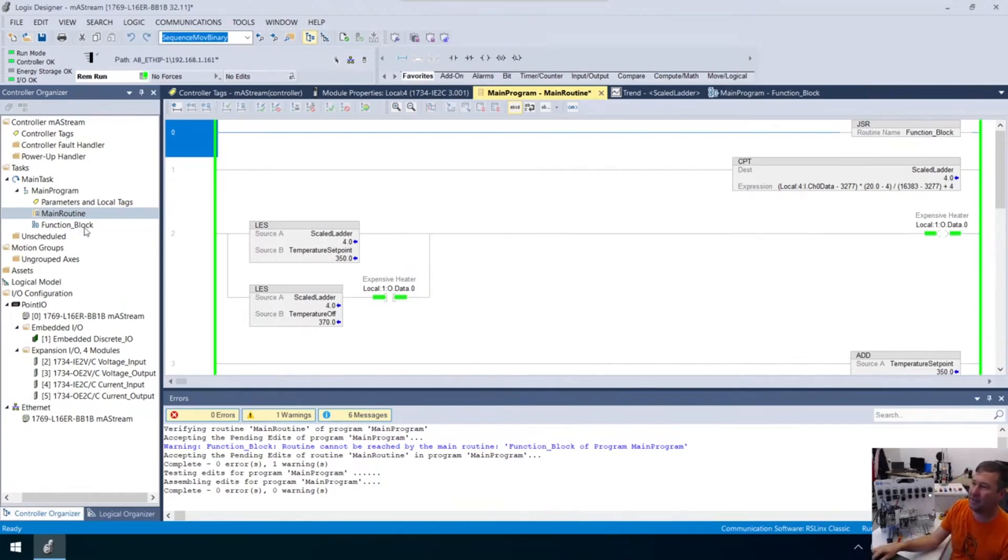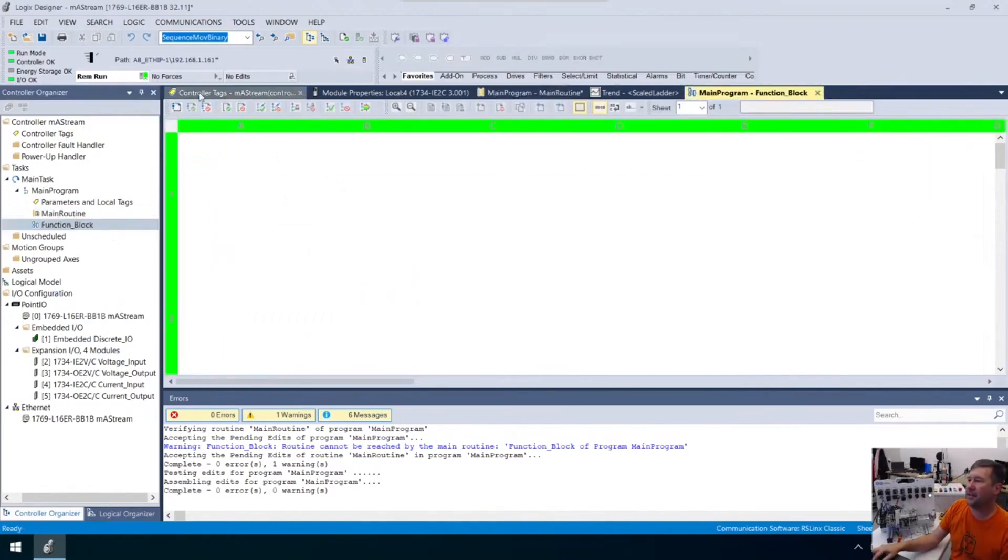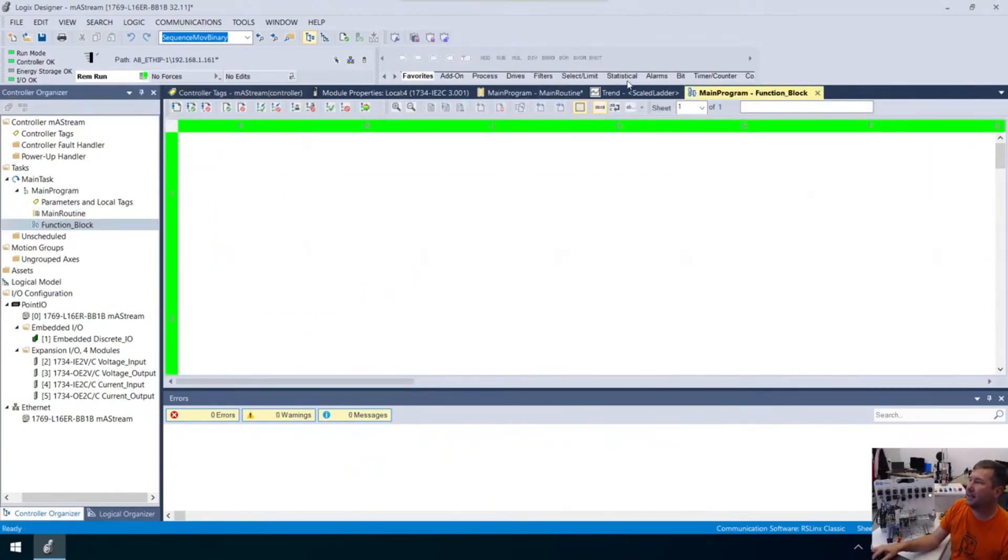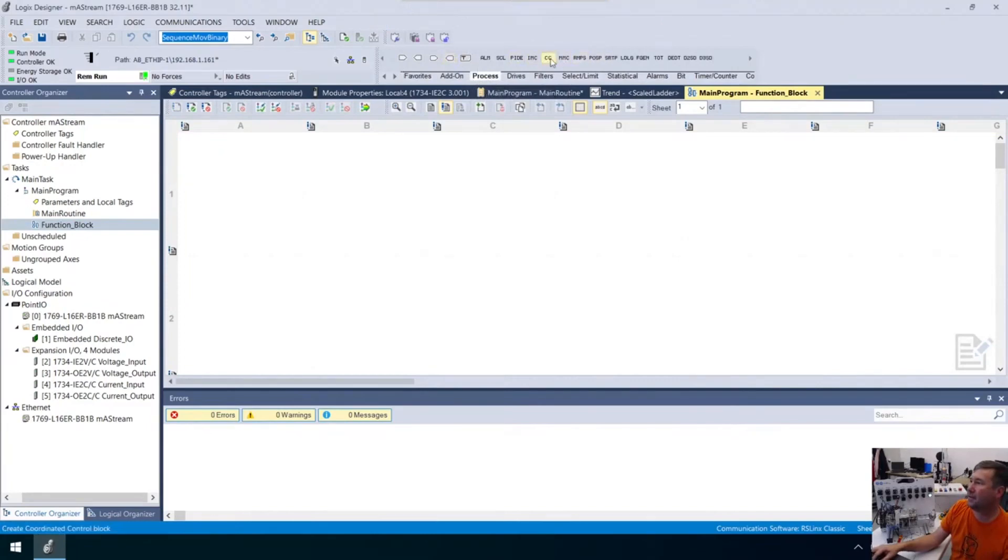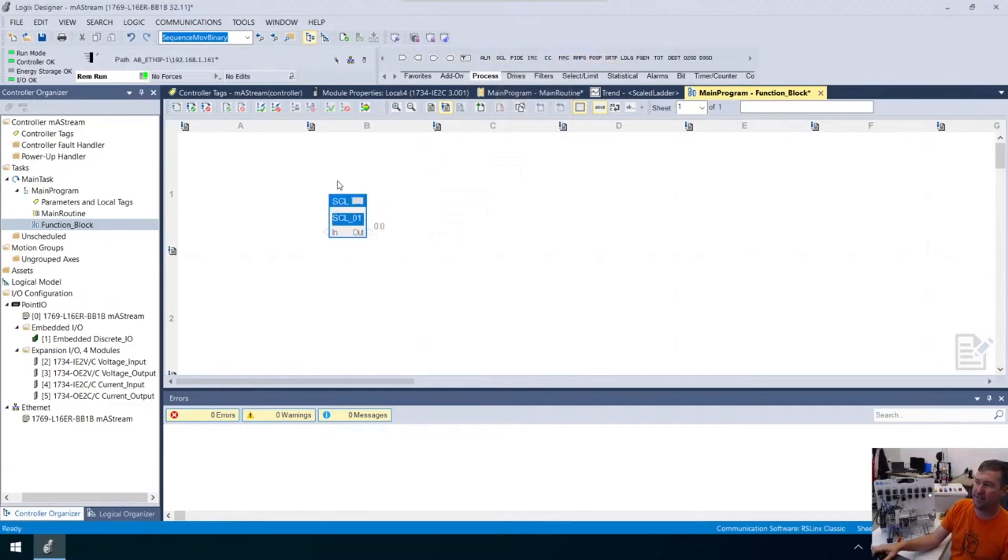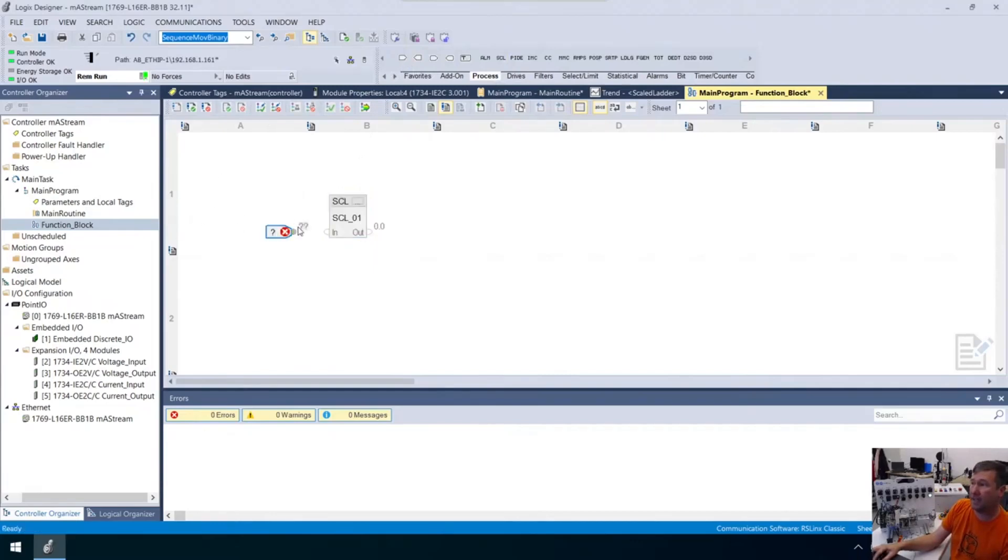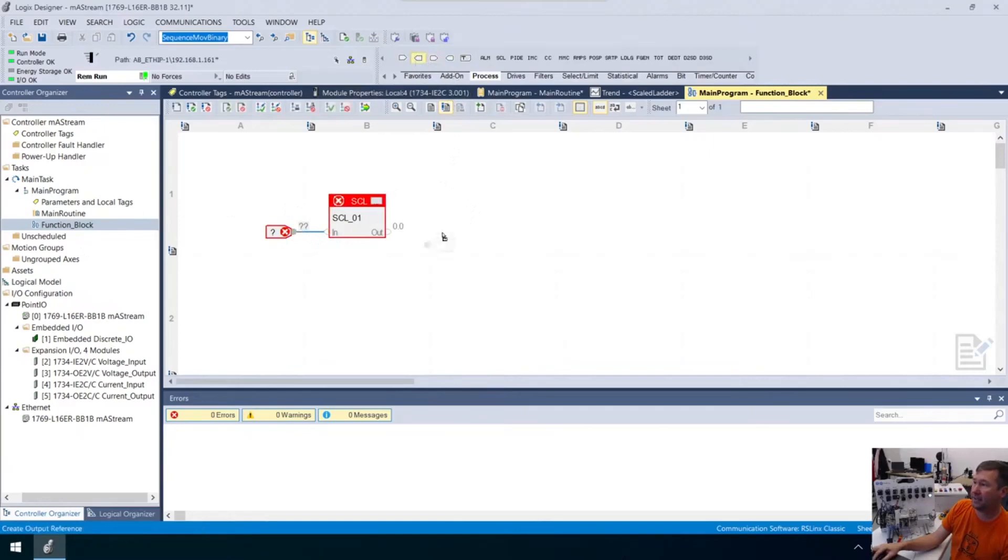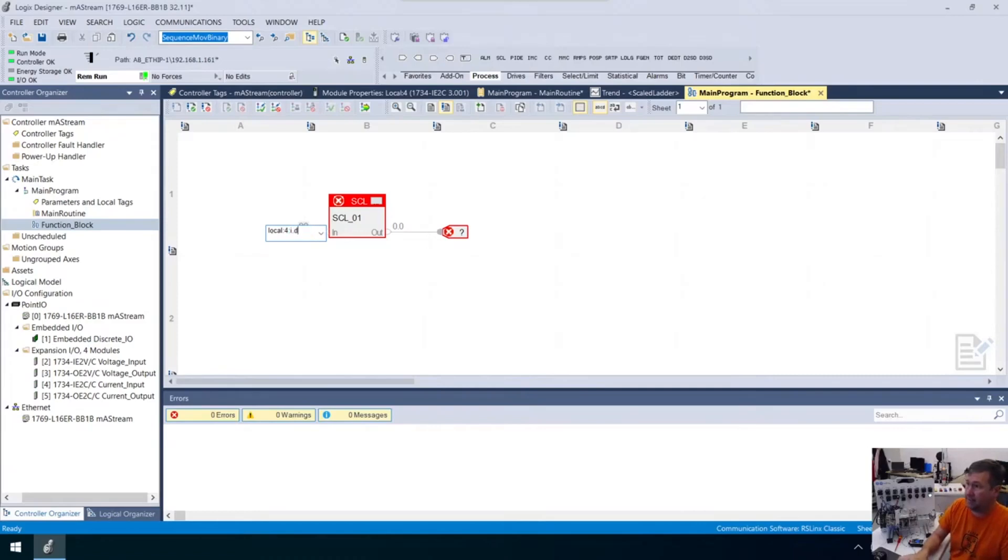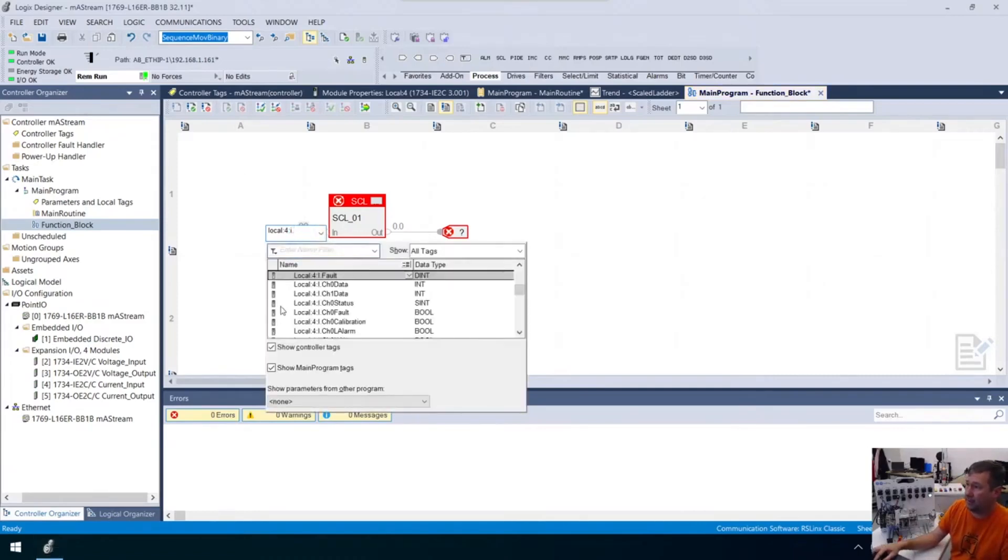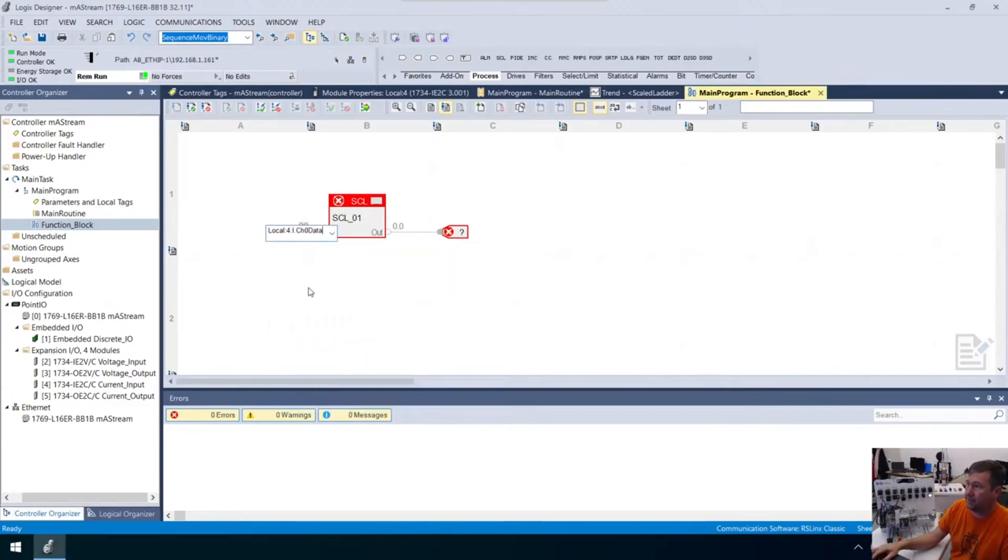Let's talk about how we do this in a function block. We go to edit, then to our process tab. The second one is our SCL instruction, our scale instruction. You see we have an in and an out. Our in is what we want to scale, and that was our raw value. I'm going to drag that and connect those. Then we're going to do the same thing on the other side with an output. We're going to have local:4:I dot channel zero.